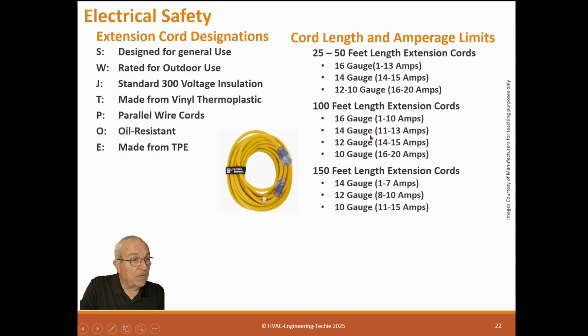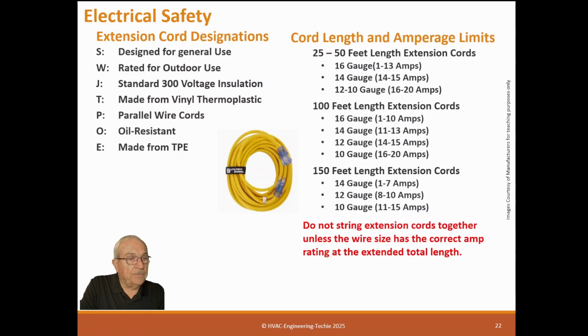So what we're talking about here is if you have a 100-foot cord and you want to put two of them together, you can make a 200-foot cord, but this 12 gauge is no longer 15 amps, it's 7 amps if it's 200 feet long. So you need to remember that the amperage goes down with the length of the extension cord. Do not string extension cords together unless the wire size has the correct amp rating at the extended total length. So that's why we try to use one cord most of the time, not two.